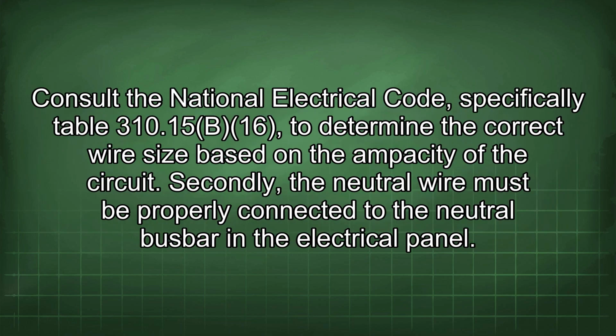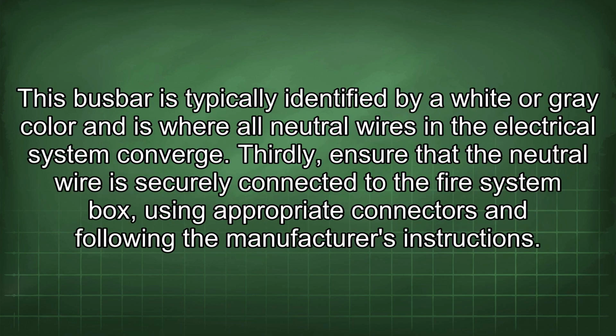Consult the National Electrical Code, specifically Table 310.15(B)(16), to determine the correct wire size based on the ampacity of the circuit. Secondly, the neutral wire must be properly connected to the neutral busbar in the electrical panel. This busbar is typically identified by a white or grey color and is where all neutral wires in the electrical system converge.